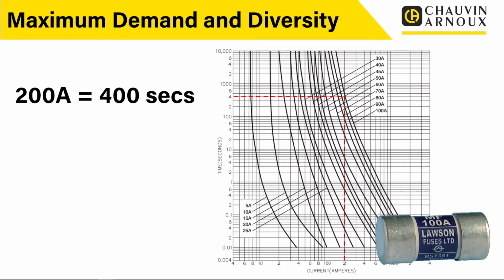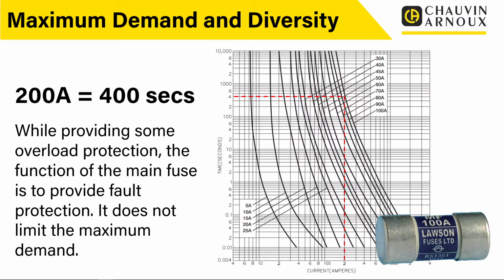So if we were overloading the installation to say, I don't know, 120 amps, 130 amps, 140 amps, it would very likely almost not go at all if you follow the graph on here. So while it does provide some overload protection, obviously if we severely overloaded it, it would go. The function of the main fuse is to provide fault protection. So if you've got a serious fault, a few thousand amps, it's going to go quickly and disconnect your installation. And that's what it's there for. It doesn't limit the maximum demand. Maximum demand is about what's actually being used in the installation.